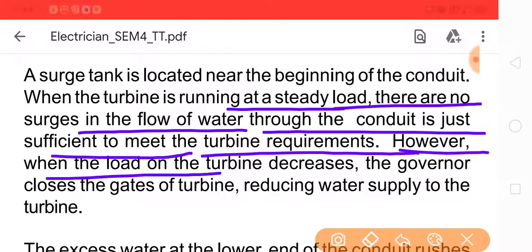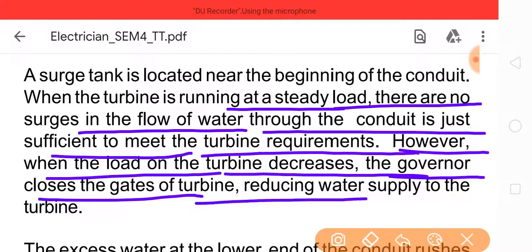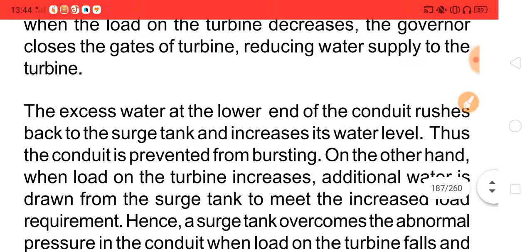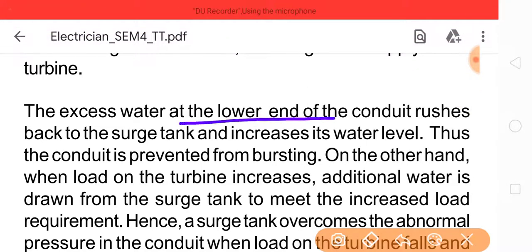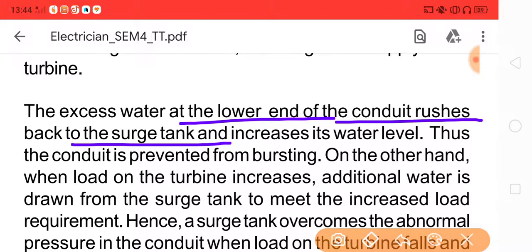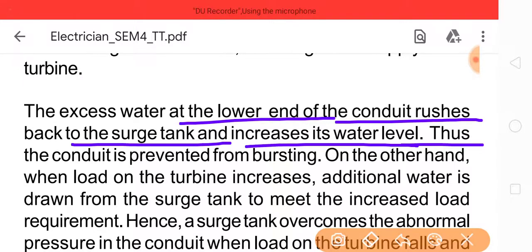However, when the load on the turbine decreases, the governor closes the gates of the turbine, reducing the water supply to the turbine. The excess water at the lower end of the conduit rushes back to the surge tank and increases its water level. Thus, the conduit is prevented from bursting.